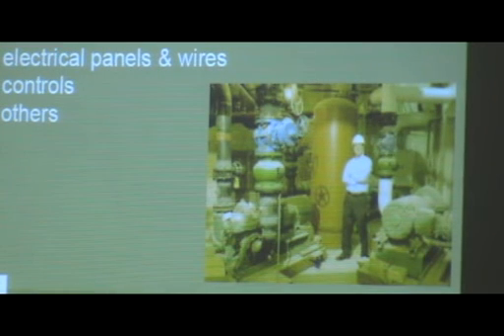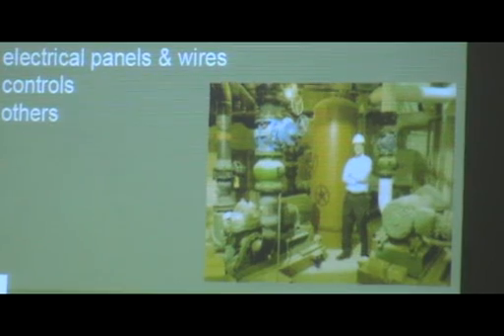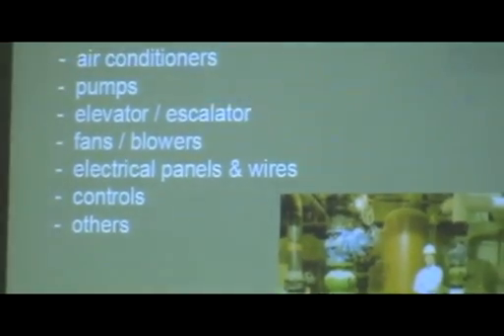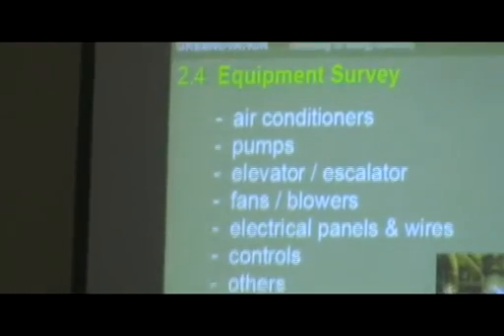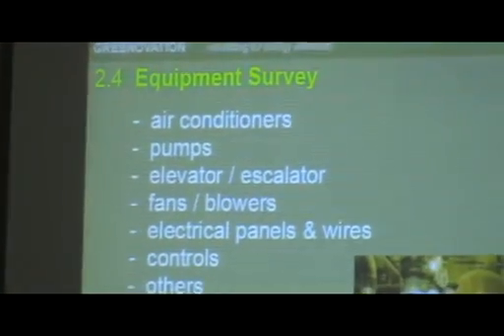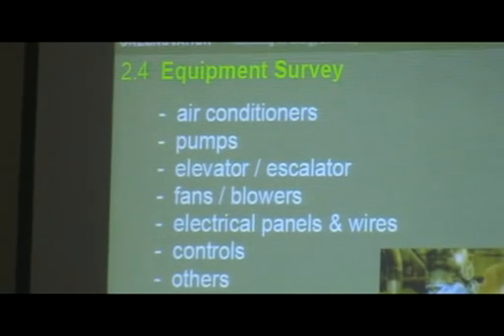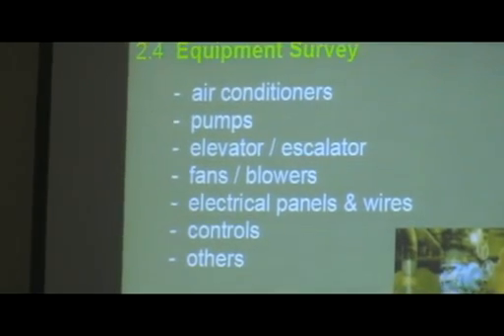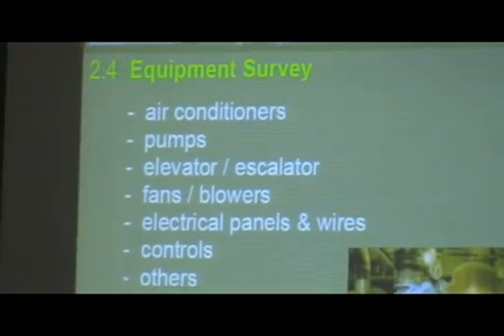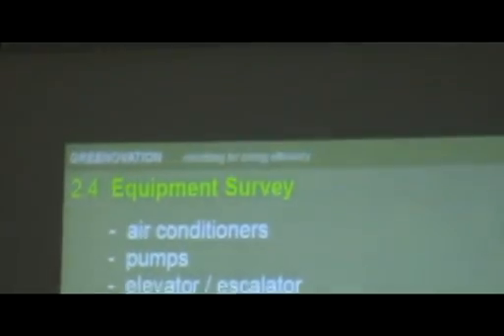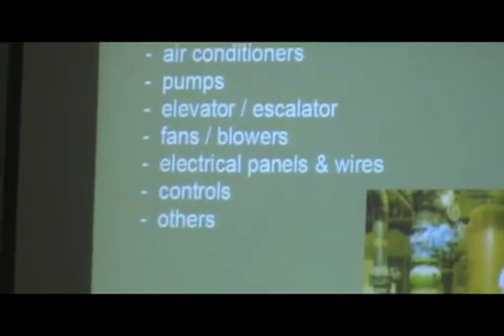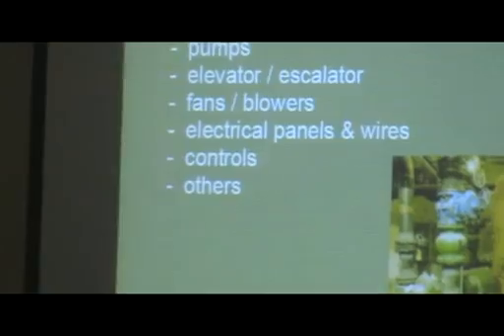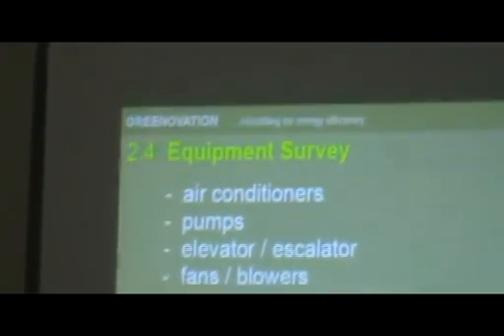Equipment survey: find out the condition of your aircons, pumps, elevators, fans, blowers, electrical panels, wires, controls, and others. Two things to check: first, the operational cost — how much electricity each piece of equipment is consuming. And second, the maintenance cost, because this will tell you if you're spending more than necessary trying to maintain a piece of equipment.